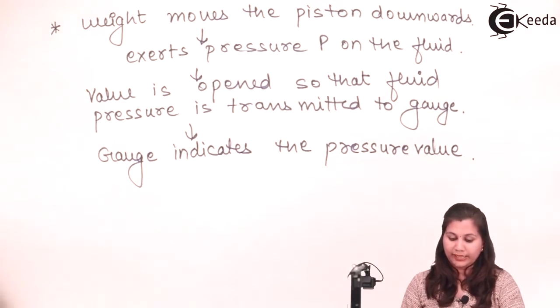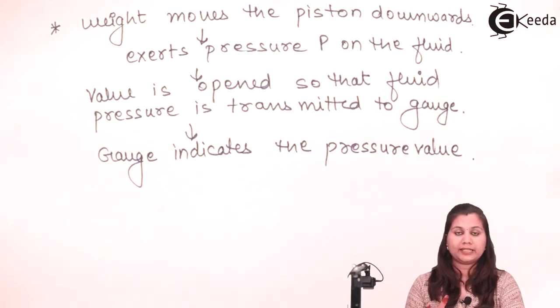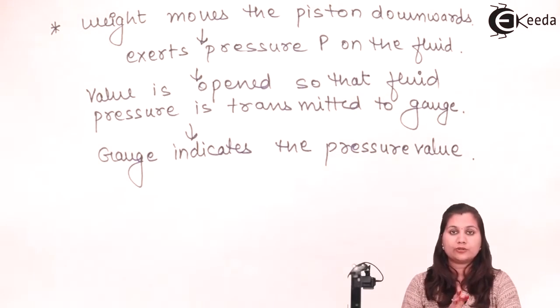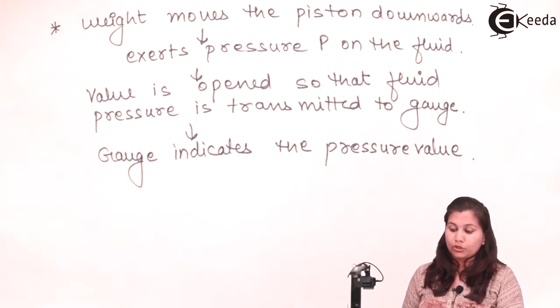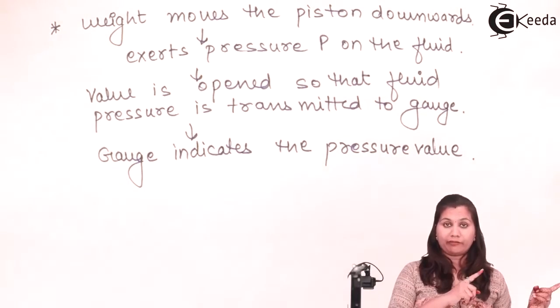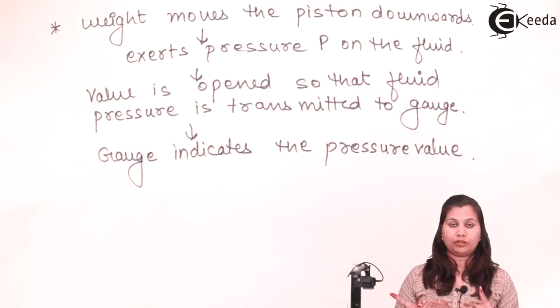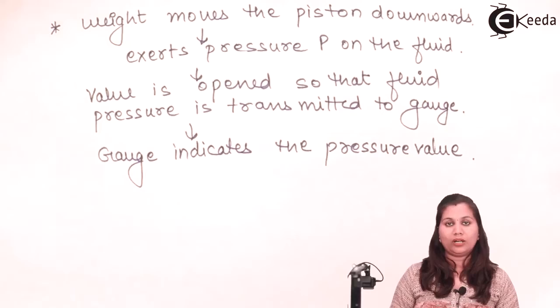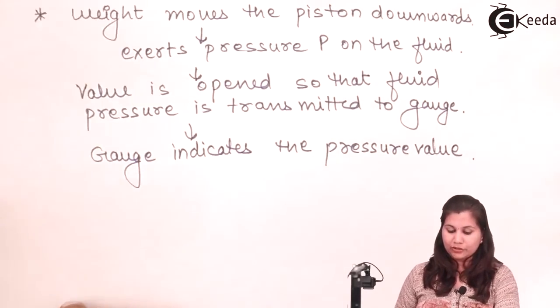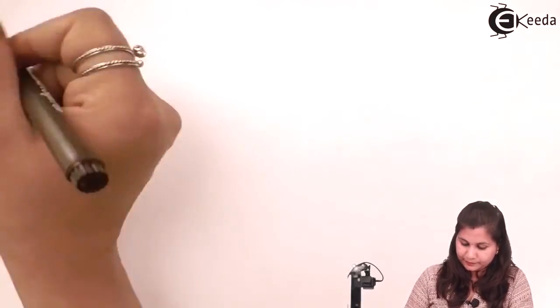So in this way, the deadweight tester is calibrating the pressure gauges and it is used for the calibration of pressure measuring devices. Okay, so here also you can see that when the reference weight and the fluid pressure are equal, the known weight is dead. That is why it is called a dead weight tester. Now if we see the applications, we have seen here that the deadweight tester is used for the calibration of the pressure measuring devices.